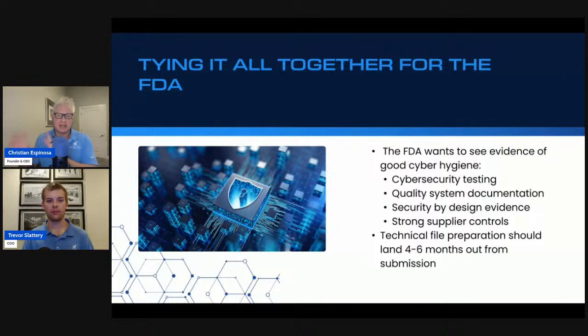It's different than traditional cybersecurity. Did you do fuzz testing? Did you do static application security testing, dynamic application security testing? Did you do a software bill of materials? So there are all these components that are required. Do you have the proper documentation as evidence as well? And that needs to go in your quality management system, as Trevor was talking about. We need the traceability from everything. The traceability that shows: here's our threat model, here's the test that validated the threat that was mitigated, and here's the evidence of all that.